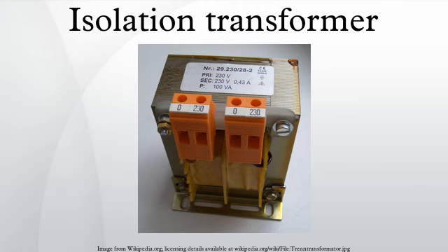Operation: isolation transformers are designed with attention to capacitive coupling between the two windings. The capacitance between primary and secondary windings would also couple AC current from the primary to the secondary. A grounded Faraday shield between the primary and the secondary greatly reduces the coupling of common mode noise. This may be another winding or a metal strip surrounding a winding.